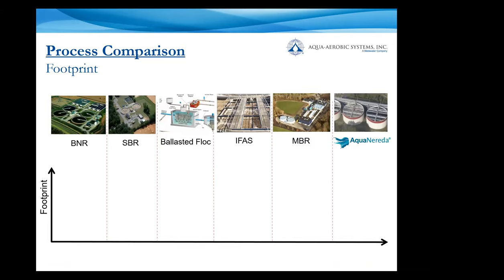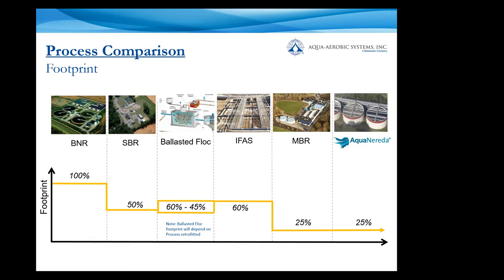And so as we look at how that applies in a practical fashion, we look at several different areas of comparison. First is footprint, benchmarking Nereda against other well-known, well-demonstrated treatment technologies. From a footprint standpoint, we look at a traditional biological nutrient removal system, which has a very large footprint for achieving those goals. Then we look at something like an SBR, a sequencing batch reactor, which achieves that same goal in about half of the footprint of a conventional BNR, similar to the ballasted floc type system, as well as an IFAS. And then when MBR came along about 20 or 25 years ago, there was another step change from a footprint standpoint, really being able to design based on a very small footprint.